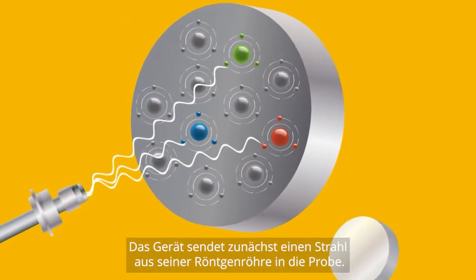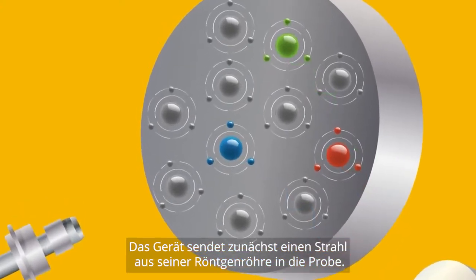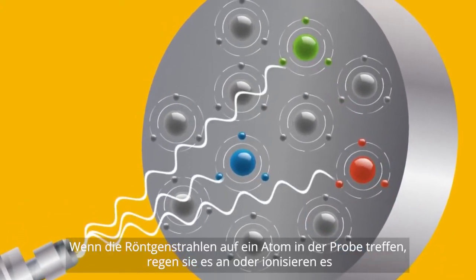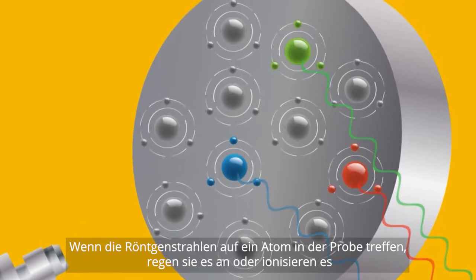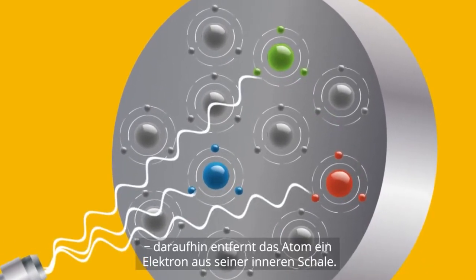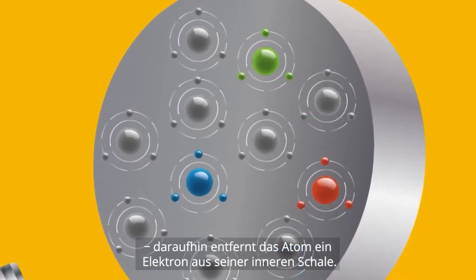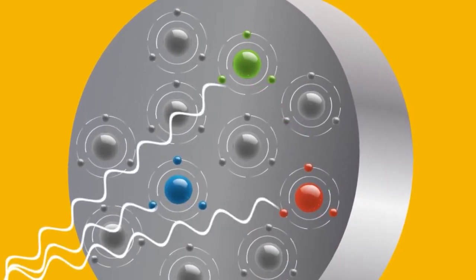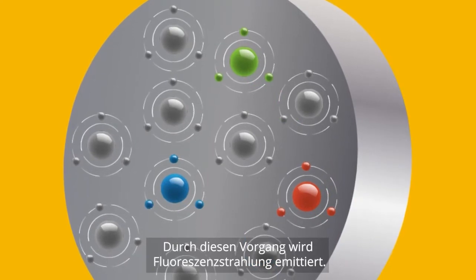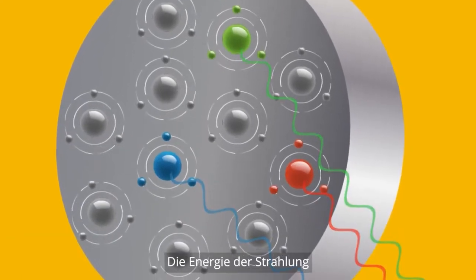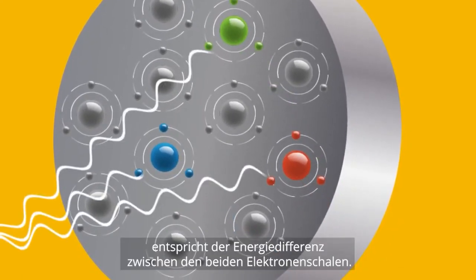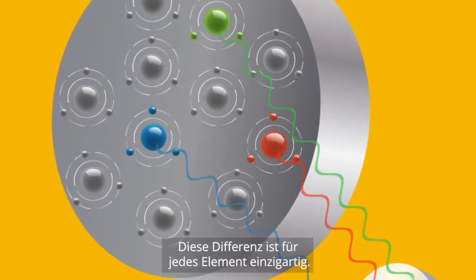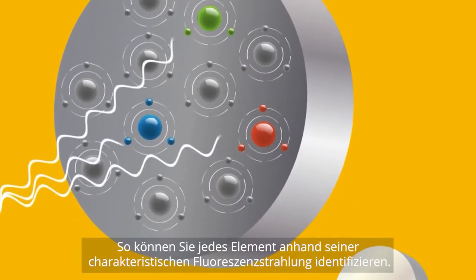How does XRF spectrometry work? The instrument begins by sending a beam from its X-ray tube into the sample. When the X-rays hit an atom in the sample, they excite or ionize it, so the atom ejects an electron from its inner shell. An outer shell electron drops down to fill the gap, and this movement emits fluorescence radiation. The energy of the radiation equals the energy difference between the two electron shells.